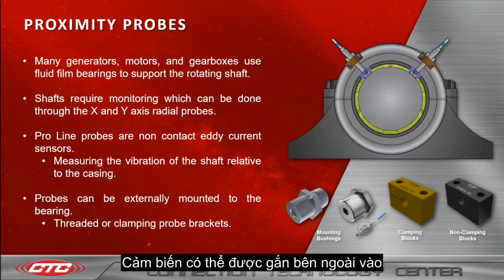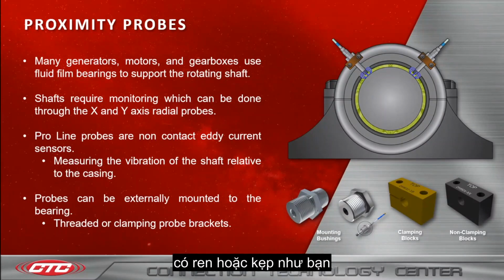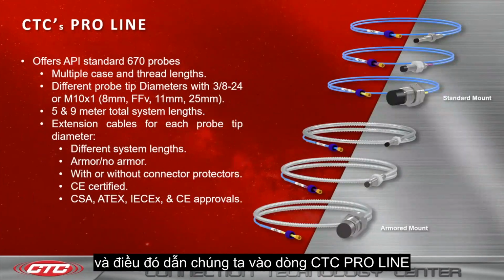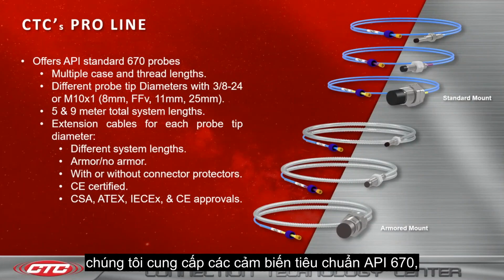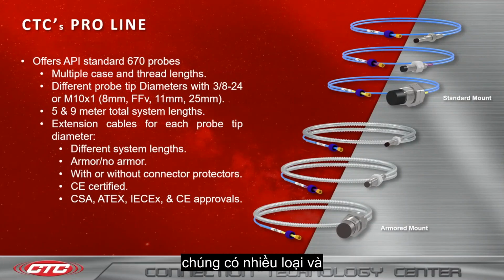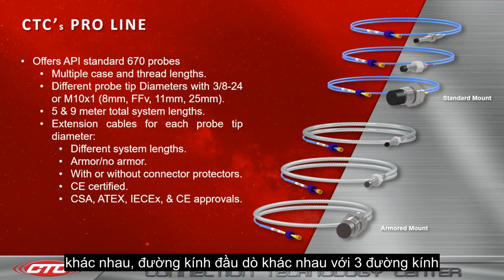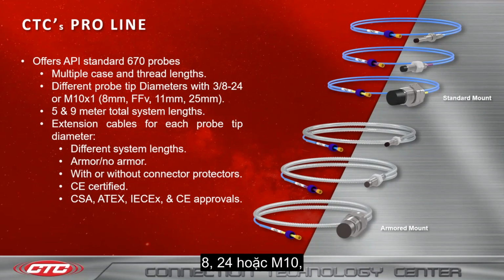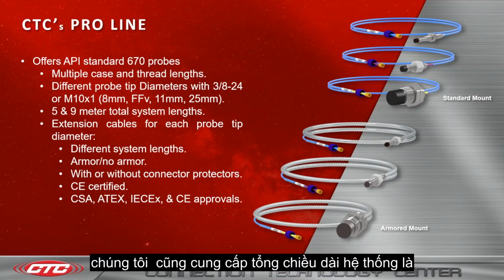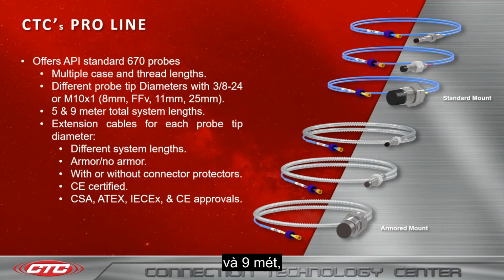Our probes can be externally mounted to the bearing, with threaded or clamping probe brackets, as you can see in the bottom right. And that leads us into our CTC ProLine. We offer API standard 670 probes. These come in multiple case and thread lengths, and different probe tip diameters with 3/8-24 or M10 threads. These come for the 8mm, FFV, 11mm, and 25mm systems. We also offer total system lengths of 5 and 9 meters.